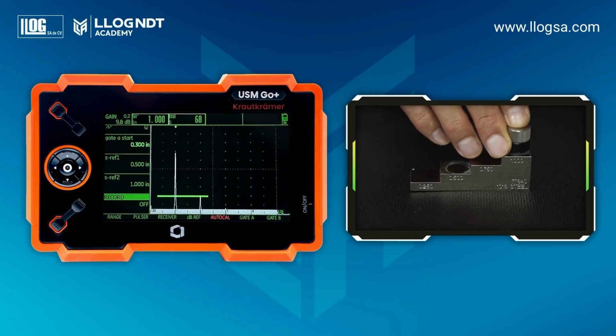Once the distance calibration is completed, the first function group will display the transducer delay value and the calculated velocity. It is important to note that when saving references during calibration, the gate must be positioned on the corresponding echo. Otherwise, the instrument will display an error message.